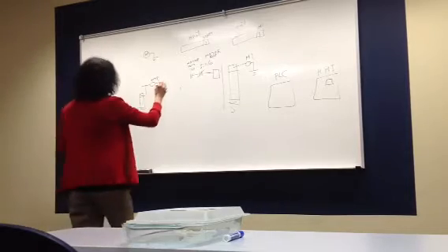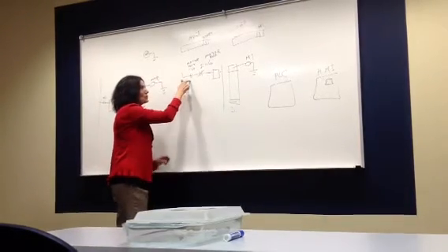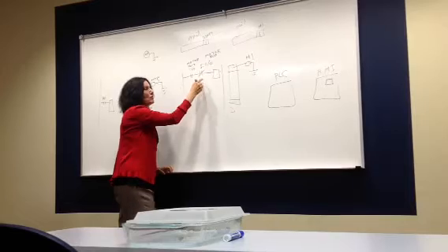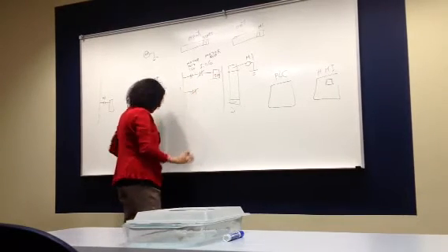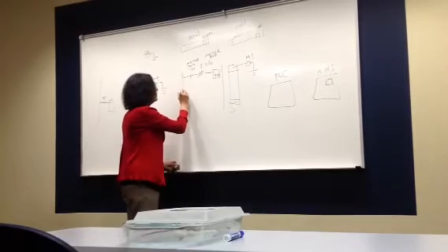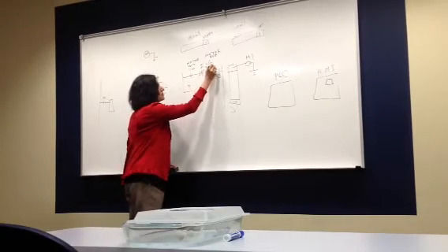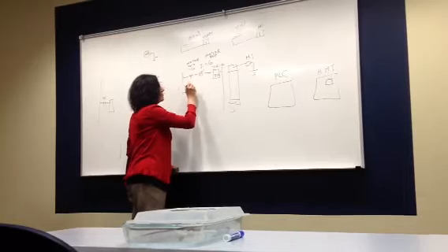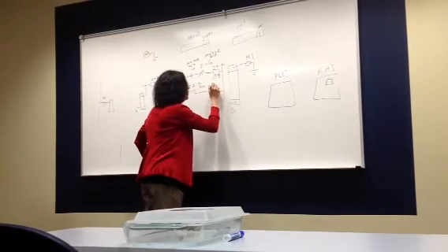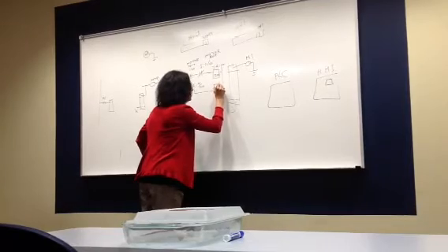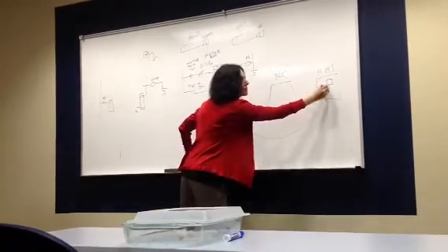So if my output is true for the motor and I don't receive the input in 5 seconds, then the done bit is true. The timer done bit, and this bit here, B3/ whatever, is the one we send.